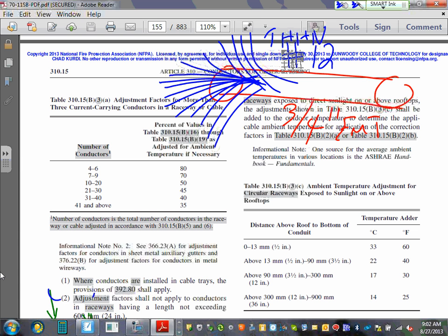I'm using these to carry lights in a commercial building. Commercial building three phase are harmonics. So the neutrals are carrying current. So each one of them, including the neutral, is a hot conductor. Each one of them, including the neutral, is a hot conductor. Okay?